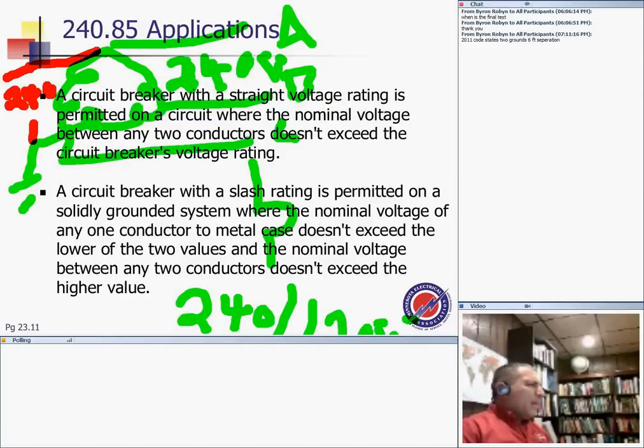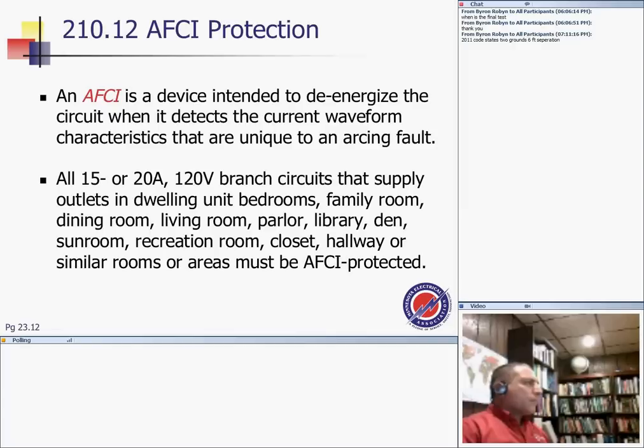So that's what they're trying to say. If you have a circuit breaker with two ratings, 240/120, anything line to neutral has to be 120 or less, anything line to line has to be 240. And now we're in a situation where it's a corner grounded delta. Any more, friends? Any questions?